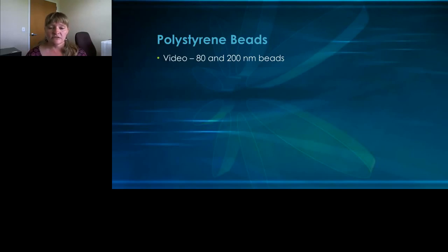Defining instrument calibration standards helps determine flow cytometry's small particle performance. There are 4 different areas I will discuss today: polystyrene beads, liposomes, purchased exosomes, and the electronic pulser. Each of these standards can be used to determine if the flow cytometer can measure and see EVs. Running polystyrene beads for initial determination of optical sensitivity to EVs is a good start. As seen in the next video after this slide, the Astrios EQ could detect 200 nanometer beads with 80 nanometer beads near the noise floor of the system.